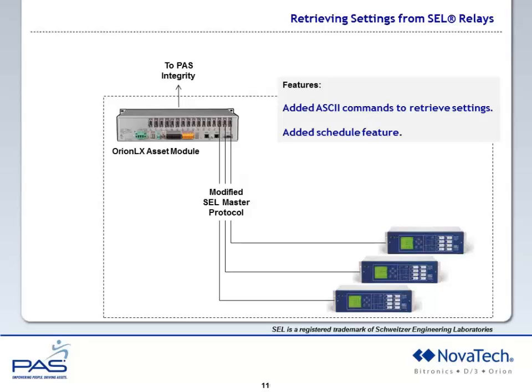Inside the substation, there's software running on an Orion LX, software specifically related to meeting NERC CIP 10, but based upon software modules that already are used in the Orion for other applications. In this case, the access of settings information from the Schweitzer relays is done with a modification of our existing Schweitzer master protocol number 14. We've added additional ASCII commands to retrieve the settings. We've also added a scheduler feature. That's designed to work with pretty much all of the relays that we currently connect to in substation automation applications.